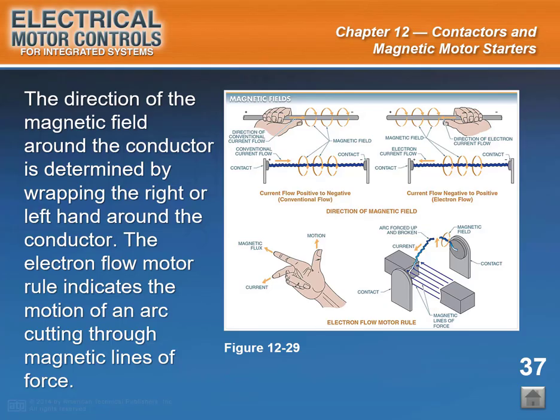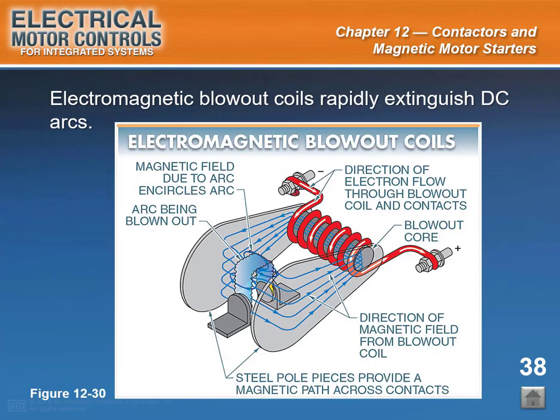End of slide 37. Start of slide 38. Slide caption: Electromagnetic blowout coils rapidly extinguish DC arcs. See Figure 12-30. The electron flow motor rule states that when a current-carrying conductor, represented by the middle finger, is placed in a parallel magnetic field, represented by the index finger, the resulting force or movement is in the direction of the thumb. This action occurs because the magnetic field around the current flow opposes the parallel magnetic field above the current flow. This makes the magnetic field above the current flow weaker, while aiding the magnetic field below the current flow, making the magnetic field stronger.